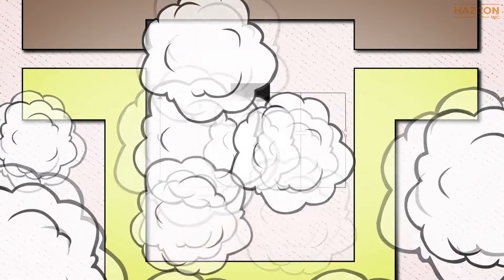Using this protection technique, ignition-capable electrical equipment is contained within an enclosure that is first purged to flush out the existing gases by submitting the enclosure to a flow of clean air or inert gas. The hazardous substances inside the enclosure are reduced to a level that would be safe in the absence of the purge.